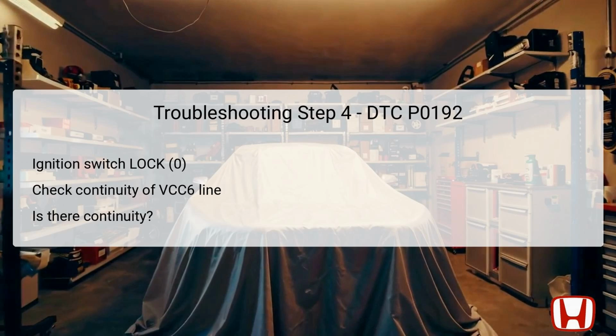If continuity exists, this indicates that the VCC6 wire is intact and functioning correctly. If continuity is confirmed, consider updating the PCM software or substituting with a known good unit if necessary. However, if no continuity is found, this suggests an open circuit in the VCC6 wire, thereby necessitating repairs.